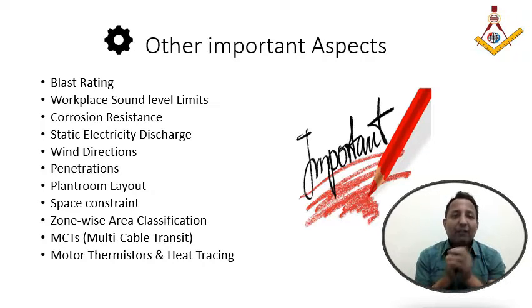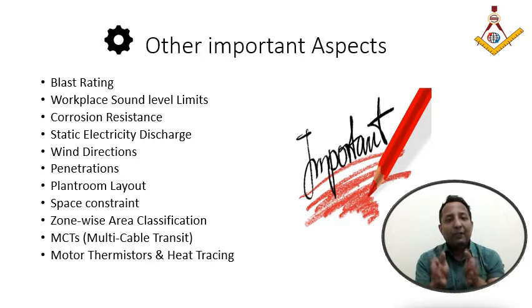So when the blast happens, a similar impact may take place over the accommodation and people will get impacted. When the study is concluded and the technical safety department says there is a danger to accommodation due to the wall, wherever there are openings of either fresh air or exhaust, it is recommended to provide blast rated walls or blast rated dampers. If you Google it, you will understand what I mean - it's a mechanical damper which is blast rated, and we need to give the blast rating to the equipment manufacturer.